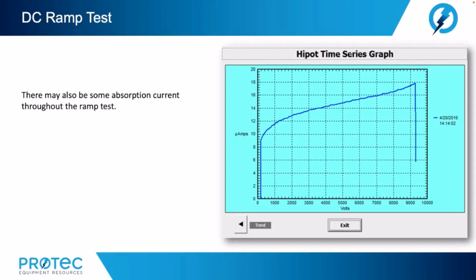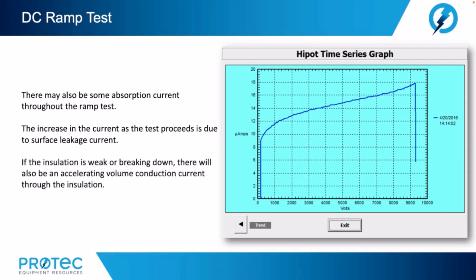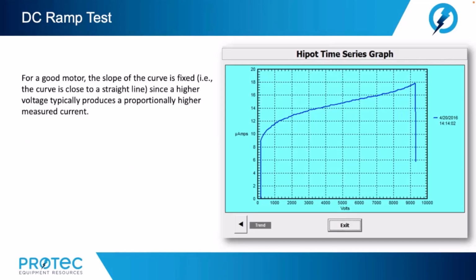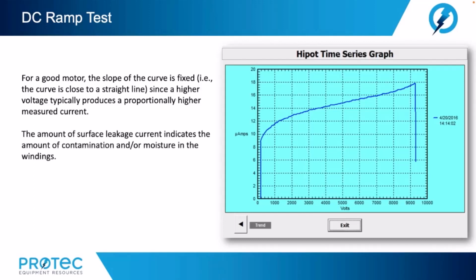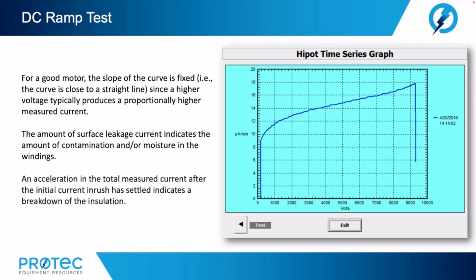Now, there may be some absorption current throughout the ramp test. The increase in the current as the test proceeds is due to surface leakage current. If the insulation is weak or breaking down, there will also be an accelerating volume conduction current through the insulation. For a good motor, the slope of the curve is fixed. For example, the curve is close to a straight line, since a higher voltage typically produces a proportionally higher measured current. The amount of surface leakage current indicates the amount of contamination and or moisture in the windings. An acceleration in the total measured current after the initial current inrush has settled indicates a breakdown of the insulation.